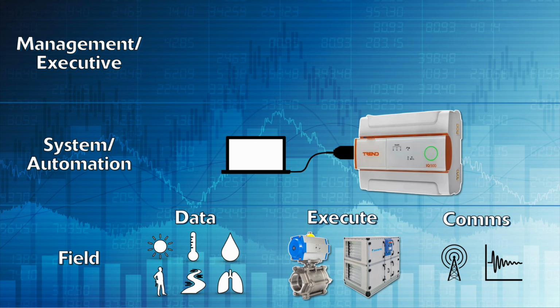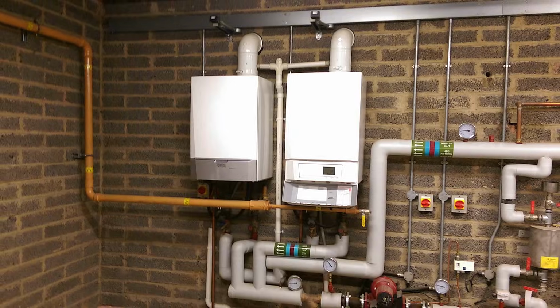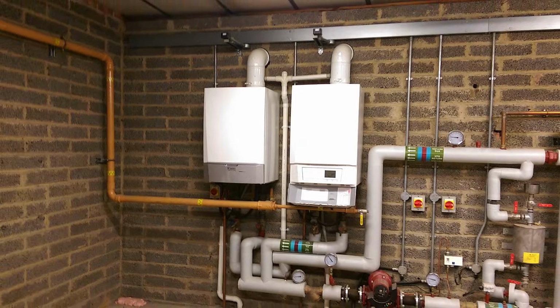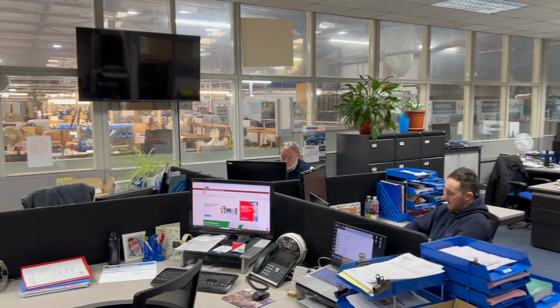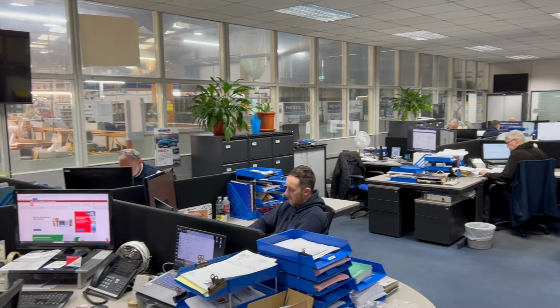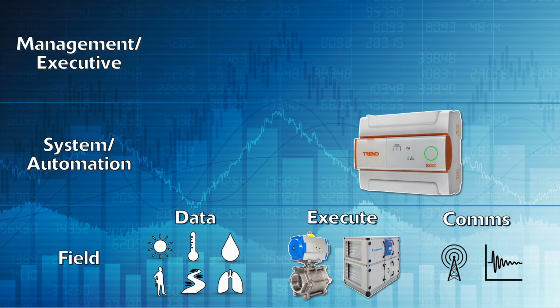Once this decision is made, the DDC carries out another of its duties by sending a signal to the field level to carry out an action, firing up a boiler or opening a valve and so on. The final duty of the DDC in the automation level is to send and receive information to and from the third level of the system, the management or executive layer. This is so called because it's the place where commands are executed or carried out.